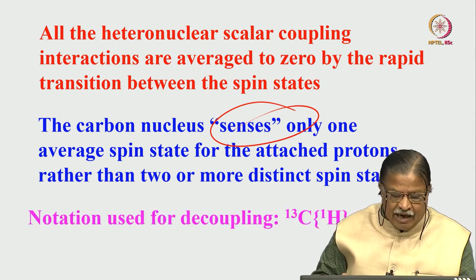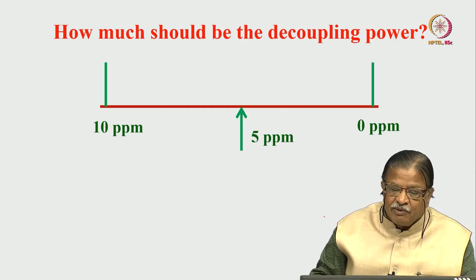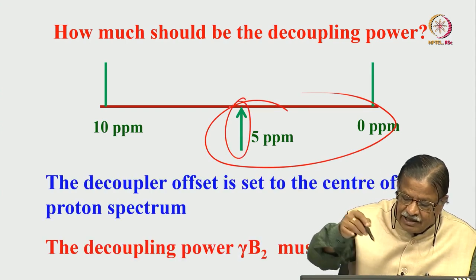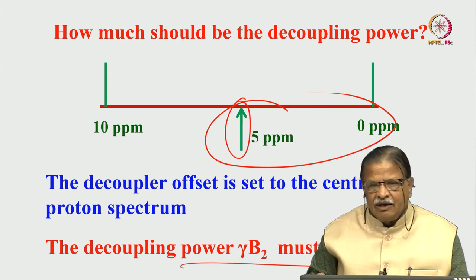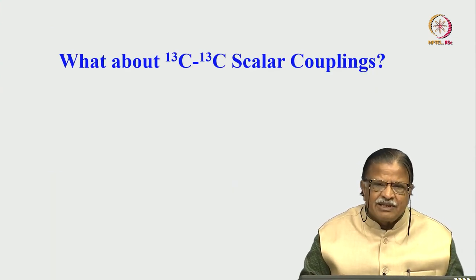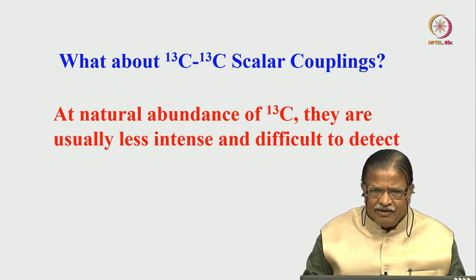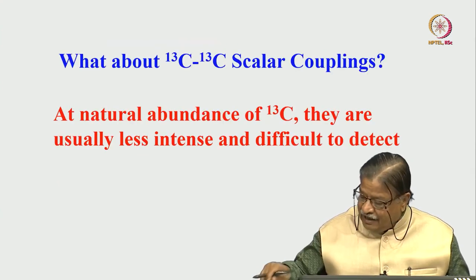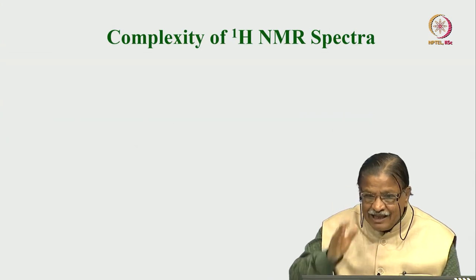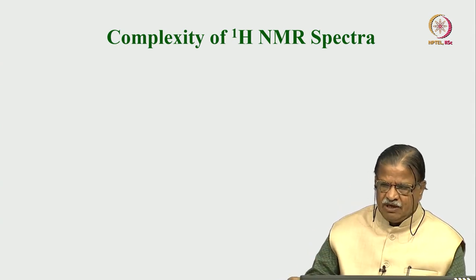As a consequence, all heteronuclear couplings are averaged to zero and the carbon senses only the average spin state for the attached protons rather than two or more distinct spin states. One can mathematically work this out, but this is the conceptual picture. The decoupling power depends upon the strength of the coupling — usually the decoupling offset is set at the center of the proton spectrum, and the decoupling power should be larger than the largest coupling strength, at least twice as large. As for 13C-13C scalar coupling, at natural abundance these are not usually visible and are very weak. Heteronuclear decoupling is easy to do. The question now is what about the complexity of the 1H NMR spectrum — this is where broadband decoupling becomes very important, and it is a topic by itself called pure shift NMR, which we will discuss in the next class.